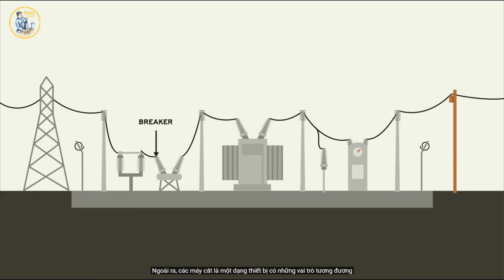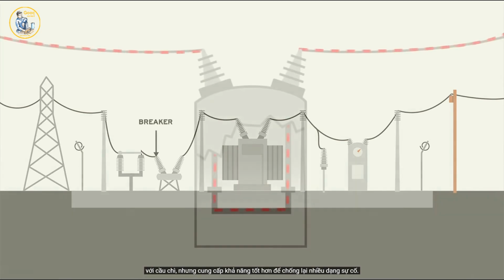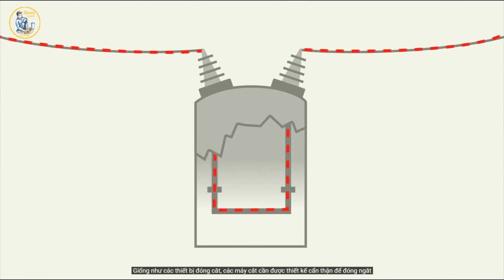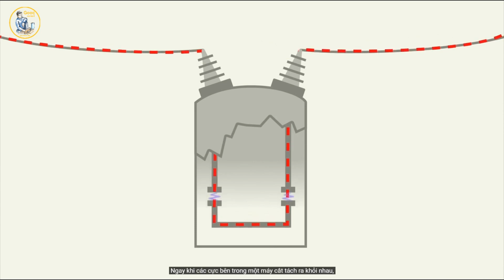On the other hand, circuit breakers are a class of device that serve similar roles as fuses, but provide more sophistication for dealing with a wide variety of faults. Like disconnect switches, circuit breakers need to be carefully designed to interrupt huge voltages and currents without damage. As soon as contacts within a circuit breaker are moved apart from one another, an electrical arc forms. This arc needs to be extinguished as quickly as possible to prevent damage to the breaker or unsafe conditions for workers.